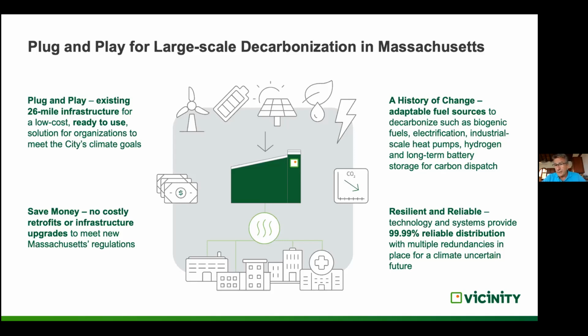Well, in fact, there are industrial heat pumps all over Europe. The largest we found is in Malmo, Sweden—a 40 megawatt heat pump, multiple stages, using very exotic refrigerants. Heat pumps can only lift the temperature so much; there's physics involved around the refrigerants and the outside air temperature, or if you're using ground sources, and ultimately you're trying to heat a building, to get air hot enough to do that. So there are some limits.